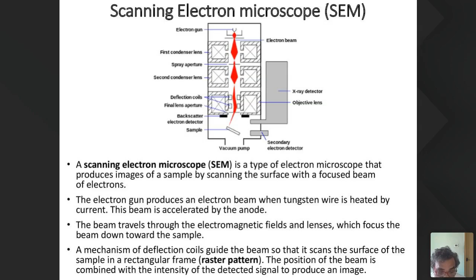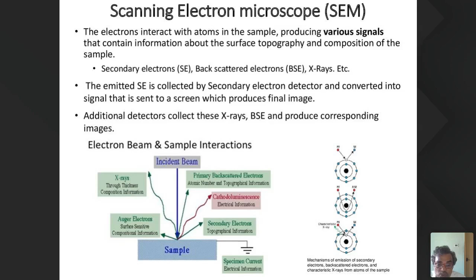The signals used by the scanning are mostly, as I told you, various signals are there, secondary electrons and backscatter electrons. The secondary electrons and the backscatter electrons are going to be useful for the study in the scanning electron microscope. Here the electron beam typically has an energy ranging from 0.2 kiloelectron volt to 40 kiloelectron volt, and is focused by 1 or 2 condenser lenses to a spot of about 0.4 nanometer. The beam passes through pairs of scanning coils or pairs of deflector plates, typically in the final lens, to deflect the beam in the XY axis so that it scans in a raster pattern.